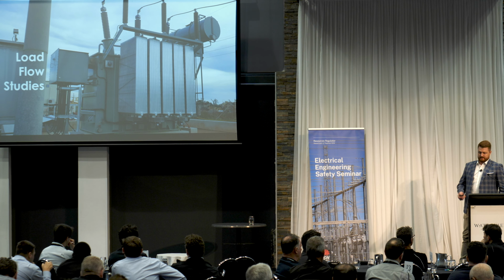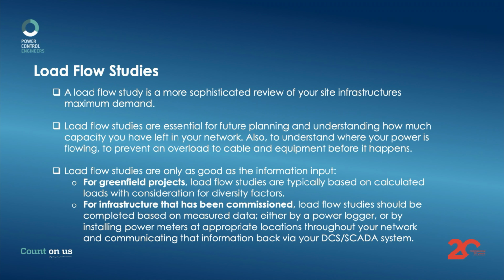Load flow studies. A load flow study is essentially a more sophisticated review of your site's infrastructure's maximum demand. Load flow studies are essential for future planning and understanding how much capacity you have left in your network. Also to understand where the power is flowing and to prevent overloads in cables or equipment before it happens or before the protection trips.